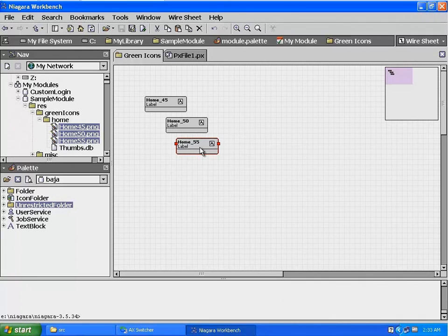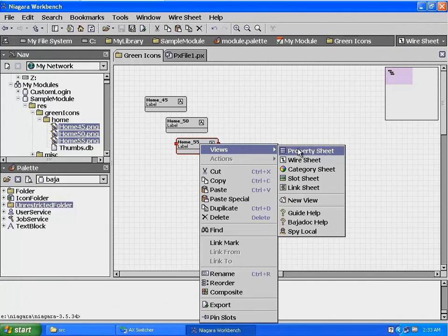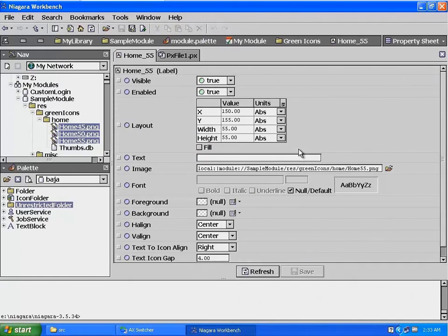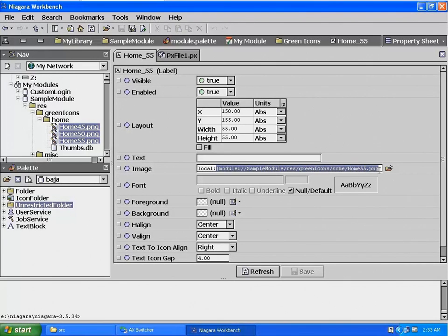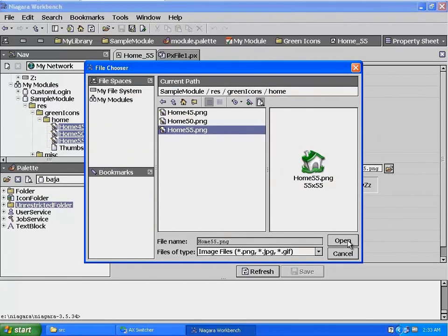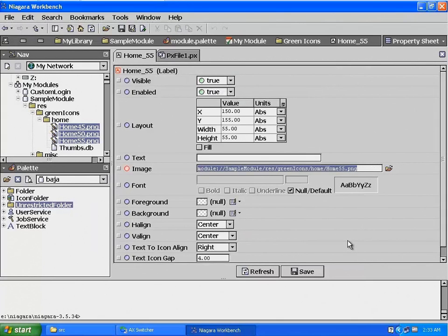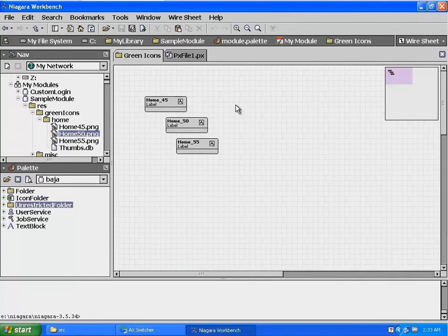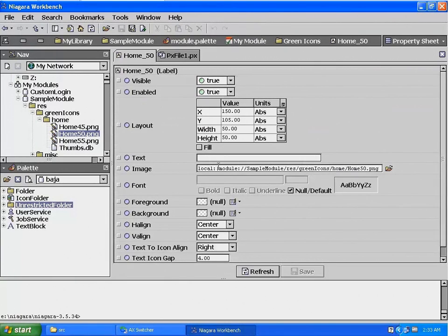Now let's take a look at the property sheet for the Home 55 image label. Highlight it, right-click, then from View, select Property Sheet. In the image path, I see an issue — the 'local:' colon should not be in the path. Let's use the directory selector to look at the correct path. Select the Home 55 image, then Open, and as you can see the correct path starts with Module. Select Save at the bottom of the property sheet to save the correct path. We will need to correct the path in the other two Home images as well.